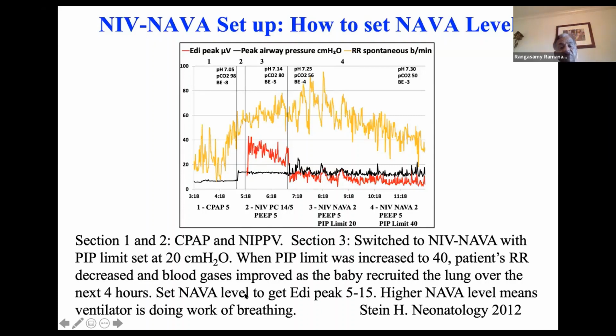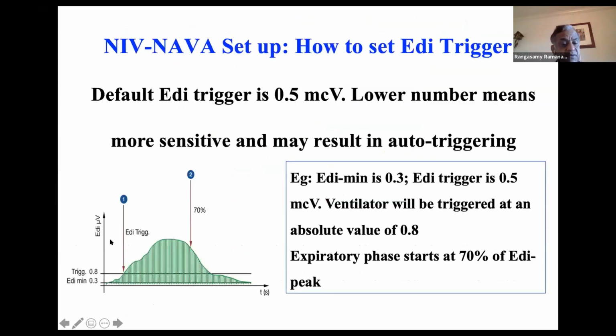So set the NAVA level to get an Edi peak between 5 to 15. Higher NAVA level means the ventilator is doing the work of breathing. I showed you in that picture, moving from patient to the ventilator. Trigger. So here is the Edi trigger. This is the minimum tonic activity of the diaphragm, in this example 0.3, and you set a 0.5 trigger. So Edi minimum is 0.3. Edi trigger generally recommended is 0.5. Okay. Lower number of trigger means it is more sensitive, and as I mentioned, may result in auto trigger.